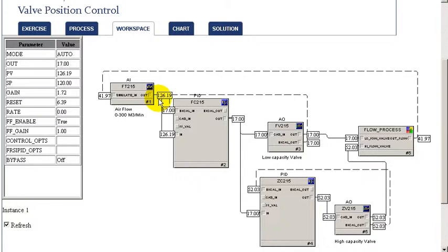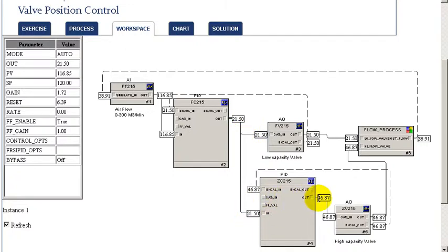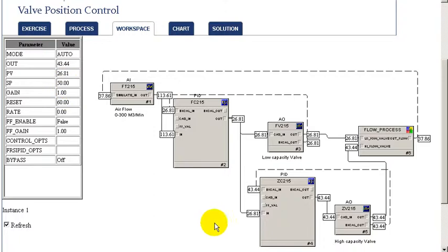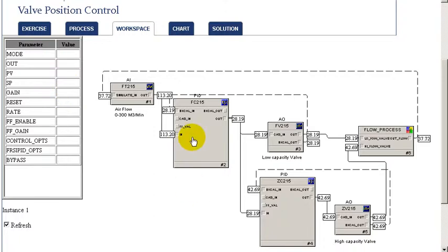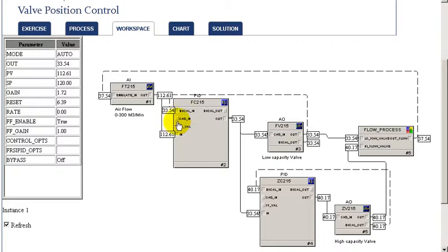In response to the output changing, the valve position PID, the integral-only PID, starts to also gradually adjust the larger valve to keep the smaller valve at the target position. Through the work of these, we're able to achieve the target flow and also maintain the smaller valve longer term at its target position.